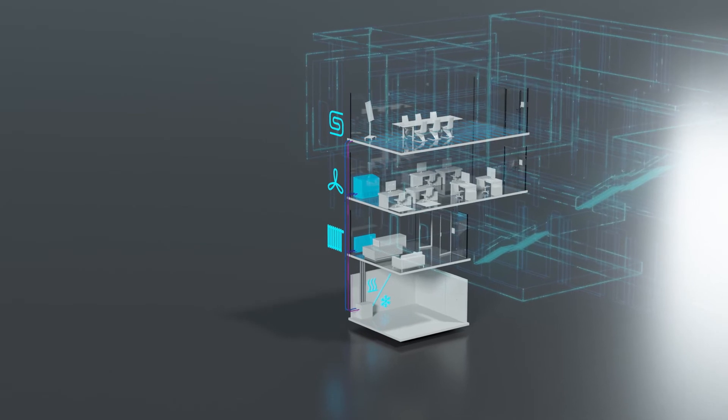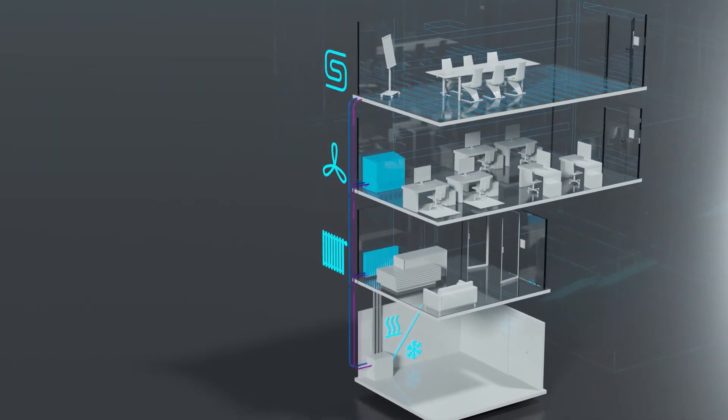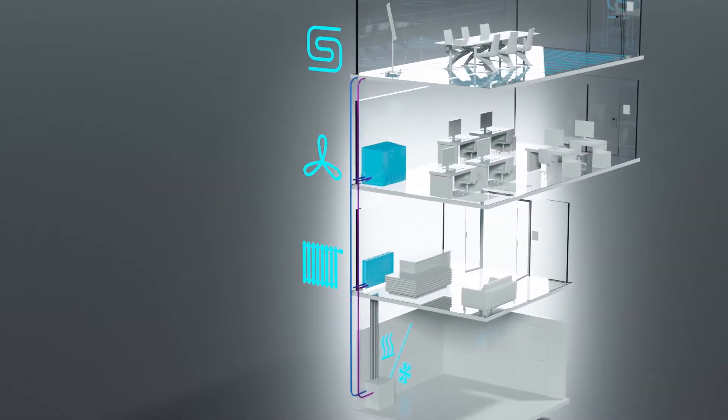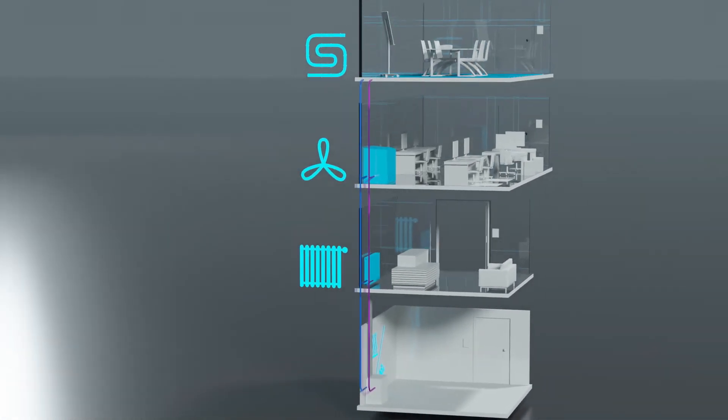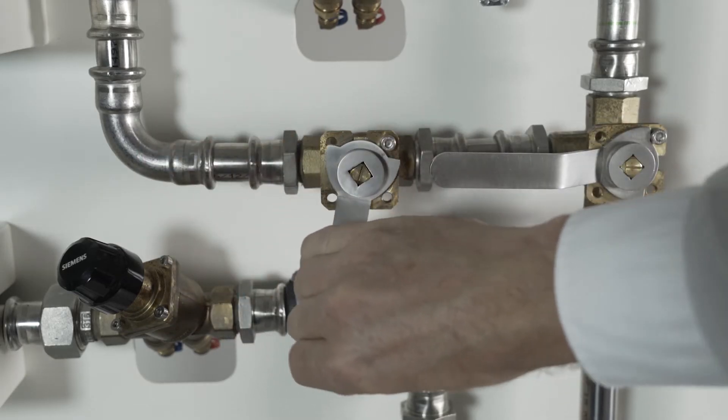Even when your heating and cooling systems have been set correctly, the actual temperatures often differ from the set points. Traditional control valves distribute a constant flow to cooling and heating coils.